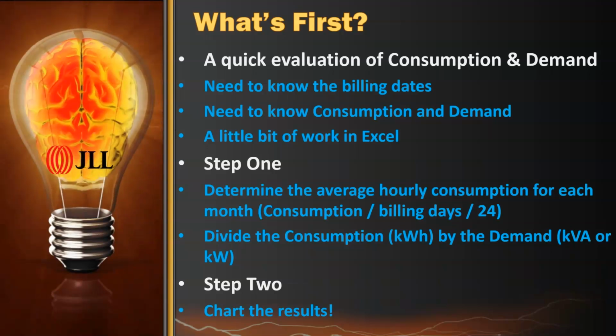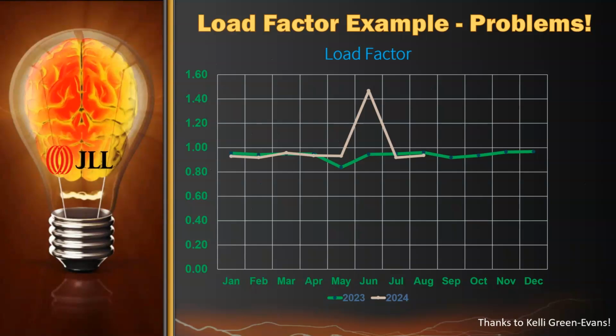And so we end up with a chart that looks kind of like this. This is actually taken from a data center. You can see that for this data center, the load factor is just slightly under 1, which, for a data center of that age, this one is 20 years old or so, really should be around 0.75. So it's elevated. That's telling me I've got a pretty high consumption number for some reason.